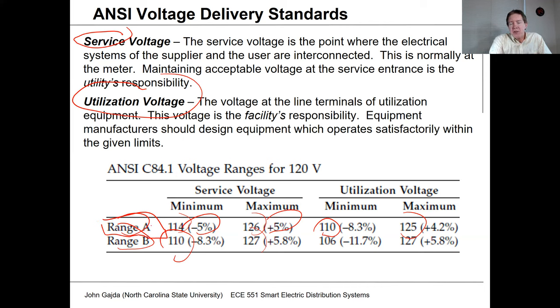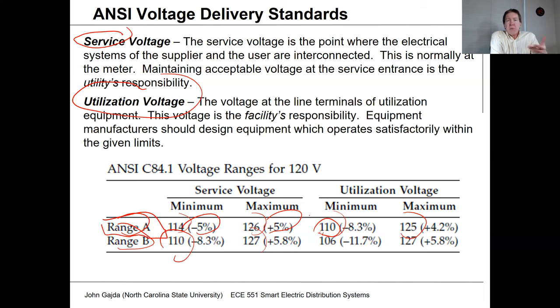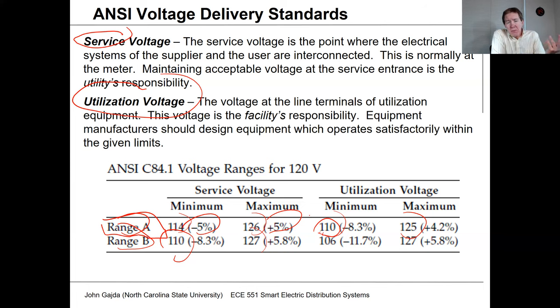Because voltage can get as low as 110 at a commercial appliance, there's some confusion when looking at device ratings. A blender listed as 115 or 110 volts is still a nominal 120V device — it's telling you it can operate as low as 110 to account for drop within a facility, but in reality it will probably see closer to 120. If the voltage gets too low, the appliance won't operate correctly — for example, a computer monitor's screen might shrink or it might trip offline.